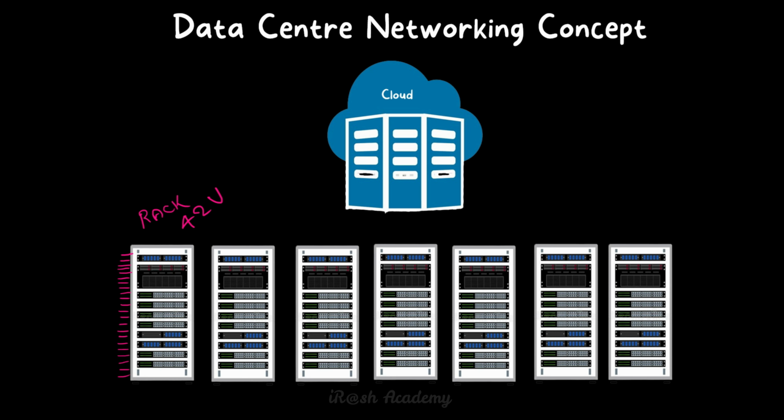Nowadays most of the devices are rack mountable devices that we can install properly inside a rack. So this rack will have a power distribution unit installed to deliver the power to the devices. They may have a redundant power distribution unit, which is called PDU. This PDU may be from electricity source 1 and this PDU may be from electricity source 2. So why do we do that? For some reason, if electric source 1 fails, the devices can still get the power from electric source 2 and vice versa. That's why we are using this redundant power supply.